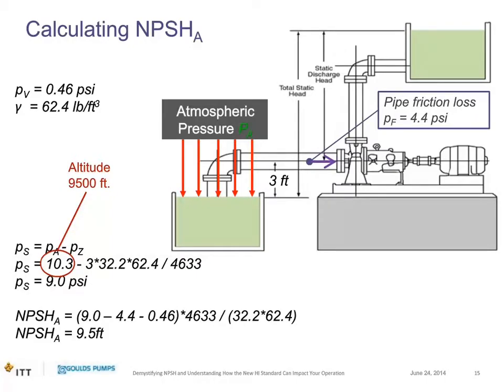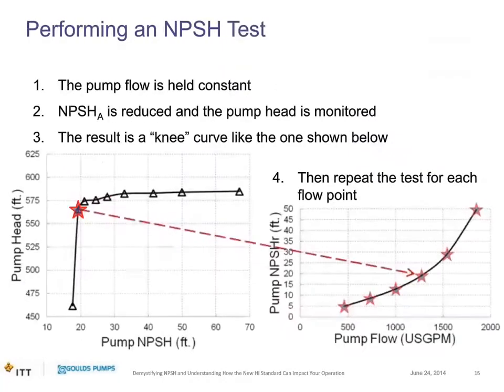Now a curve ball: the suction tank is below the pump — a lift condition — still open to atmosphere, but at an altitude of 9,500 feet. Because of the altitude, atmospheric pressure is lower at 10.3 psi. The suction pressure equation is P_atmospheric minus the static elevation (since the tank is below the pump). Converting, you get P_s = 9.0 PSI. Plugging in: 9.0 minus 4.4 PSI suction pipe loss minus 0.46 PSI vapor pressure, converted to feet, gives NPSH available of 9.5 feet.